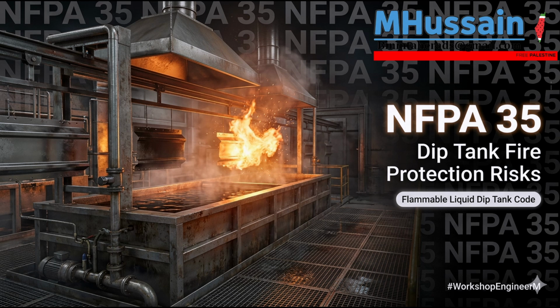First in, first out. Keep it moving. The oldest material must be used first, and the standard strongly implies it should not be stored for extended periods, generally not more than 2 years. Because over time, even in a sealed drum, that liquid wetting agent can slowly evaporate or leak out. And if a drum sits forgotten in the back corner of a hot warehouse for 3 years, it dries out.